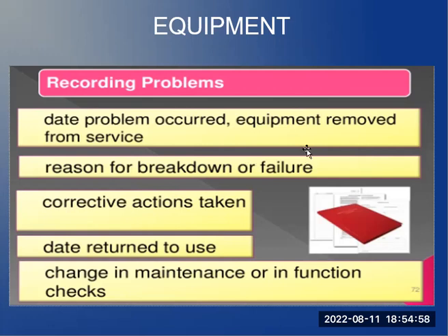So reason for breakdown or failure. Those are the four reasons: it's either the sample that clotted, the electricity or water, or the machine itself. You will know the reason in the monitor of the machine. The machine will pop up an icon showing the reason for that breakdown, like pressure error or arm error on the monitor of the machine.